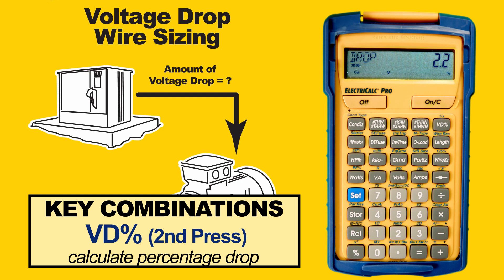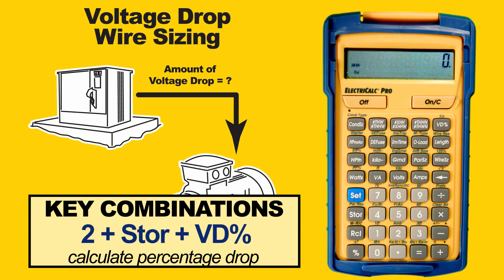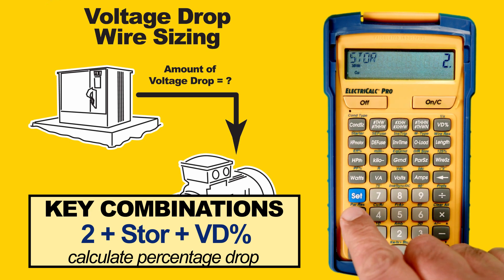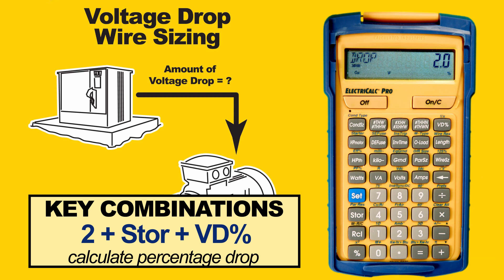Another way to use this feature is to find the maximum length you can go with a known load and wire size. For this example, we will set our voltage drop limitation to 2% by pressing 2, then Store, then Voltage Drop. We see on the screen that voltage drop is now stored at 2%. We can press Clear, but that value will stay set.